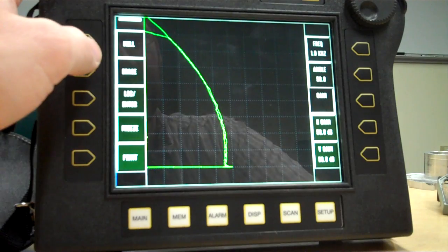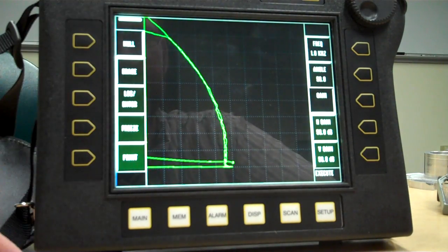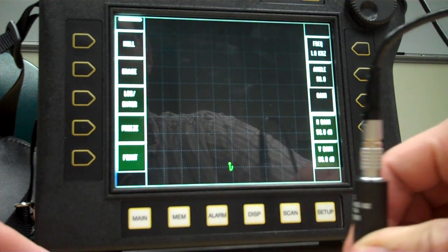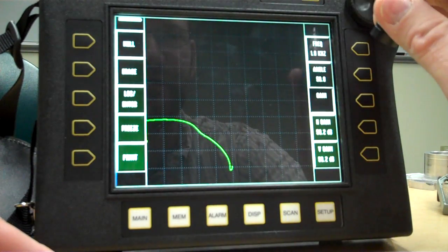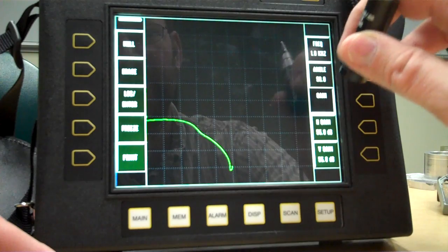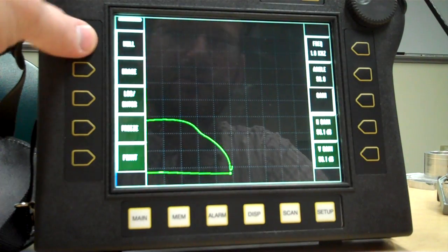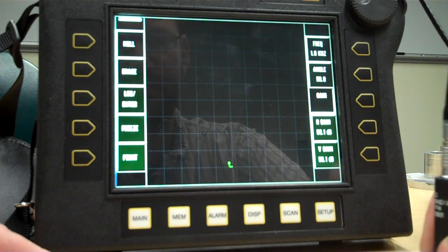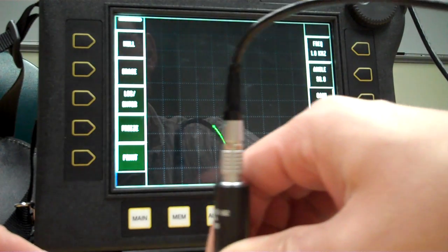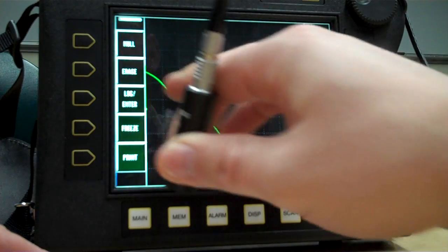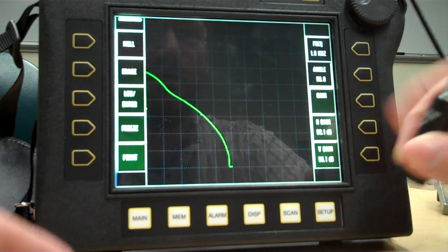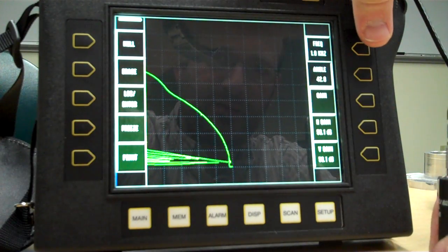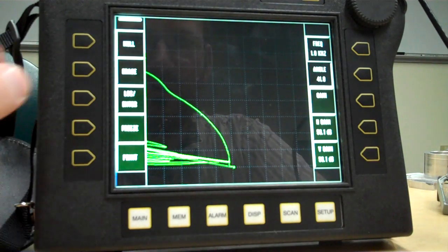And what I did was lower the frequency, so I increased the standard depth of penetration. Okay, there's my little hook thing at the end. There we go. So 50 dB is too low. Let's go about 56 and null. Okay, there's the start of my edge effect. So I'm going to take my angle just for fun. Rotate it around a little bit.